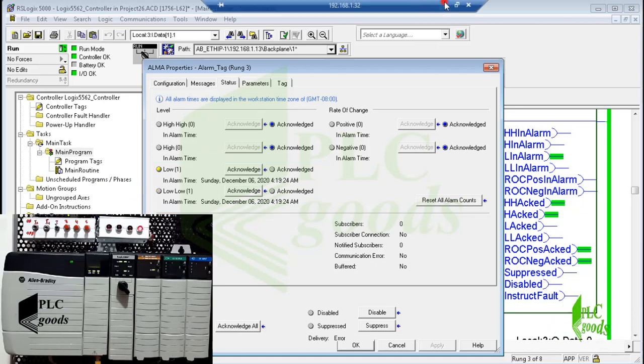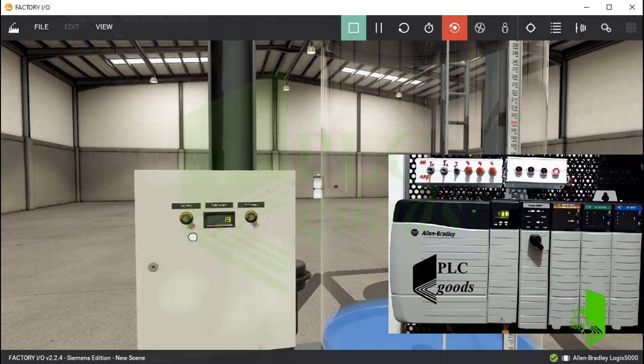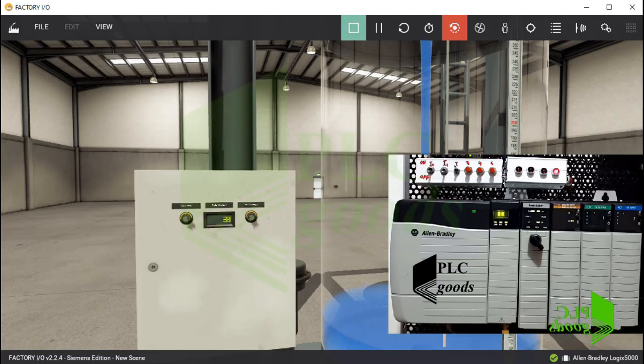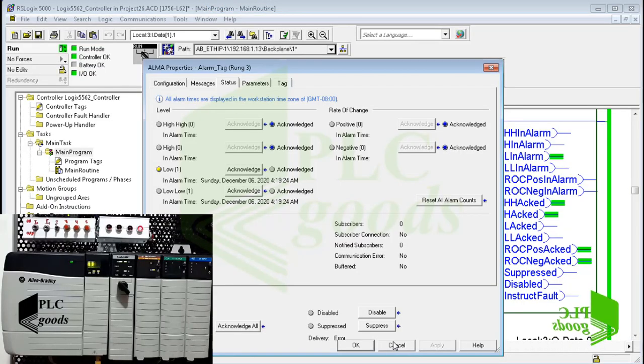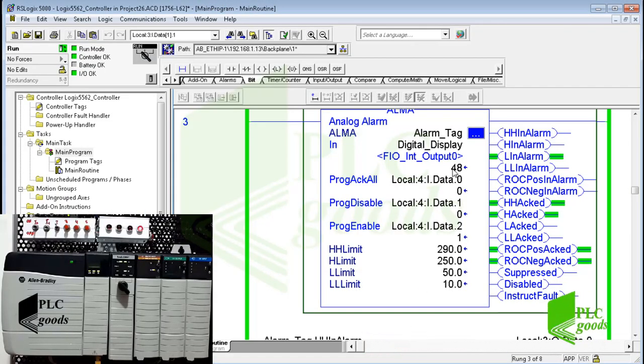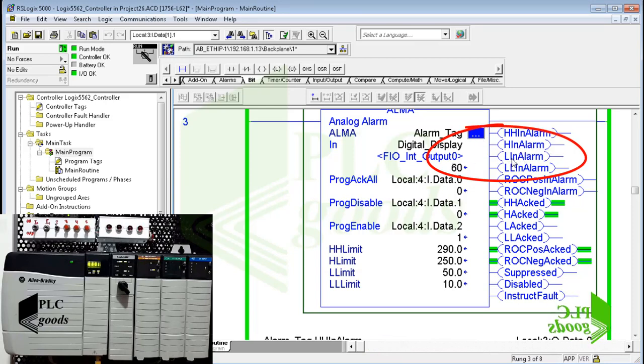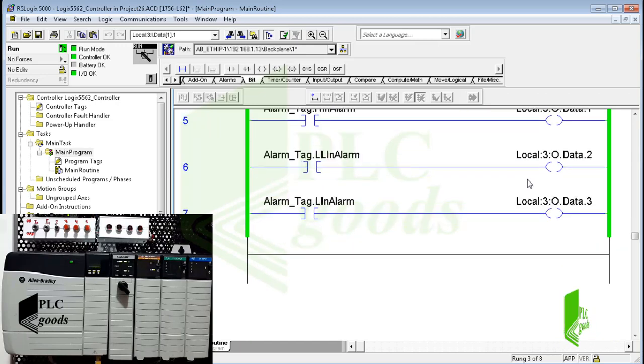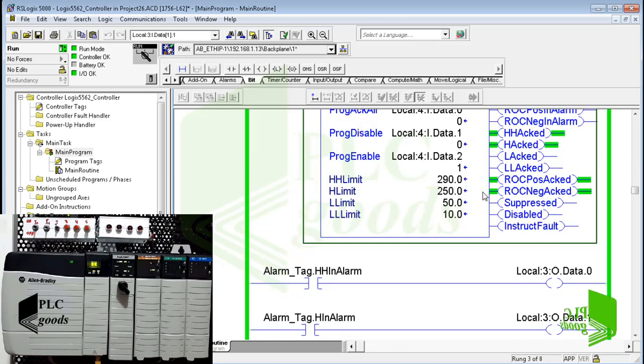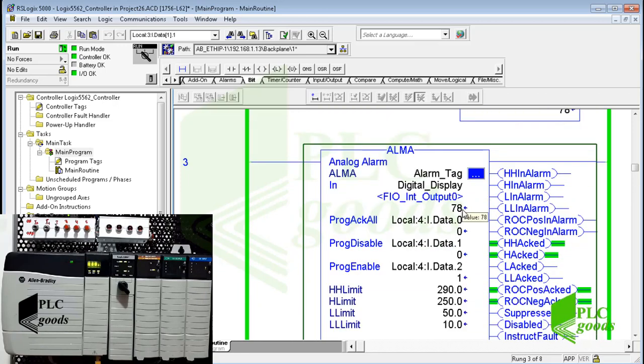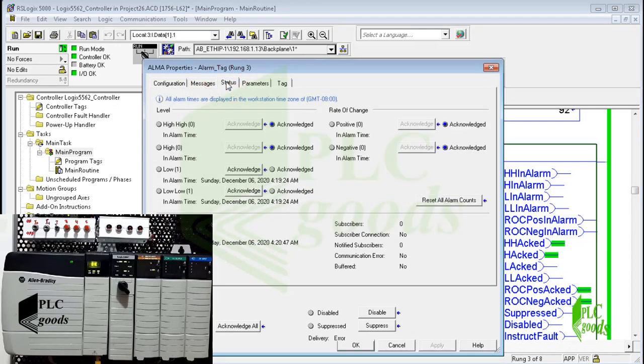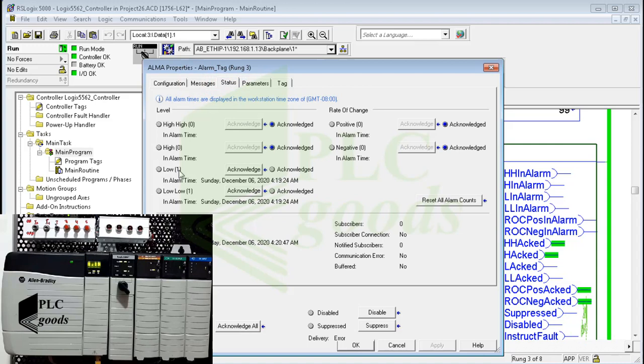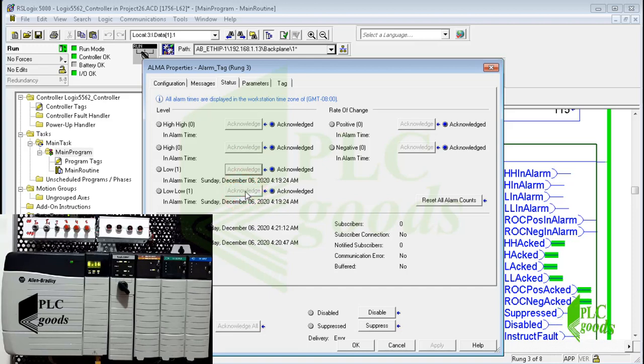Now let me open the filling valve again. Well, as the water level rises, another alarm goes off. Now there isn't any activated alarm. Note that although there isn't any alarm, but two alarms occurred before. An operator can click on each acknowledge button to confirm he has seen these alarm messages.